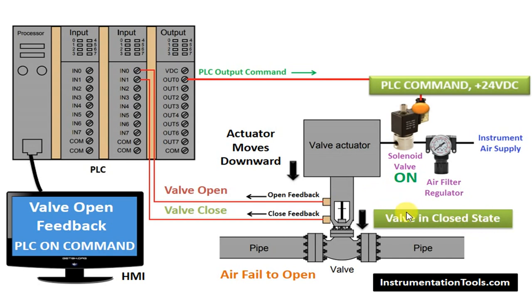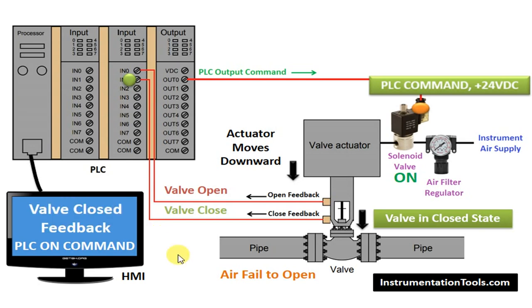So, now this change will happen. The corresponding proximity switch will be activated and send a signal to the PLC. In this case, the valve changes to closed state. So, it will send a closed feedback to the PLC. The PLC will take the closed feedback and update the graphics accordingly. Previously, the valve was shown as open in the HMI. As the signal changes, it will change from valve open to valve closed feedback. So, closed feedback is received.